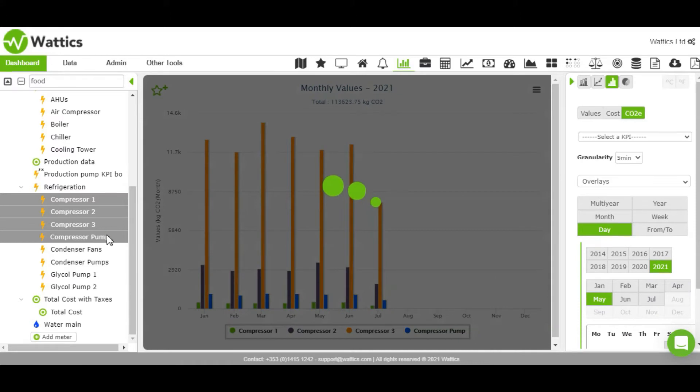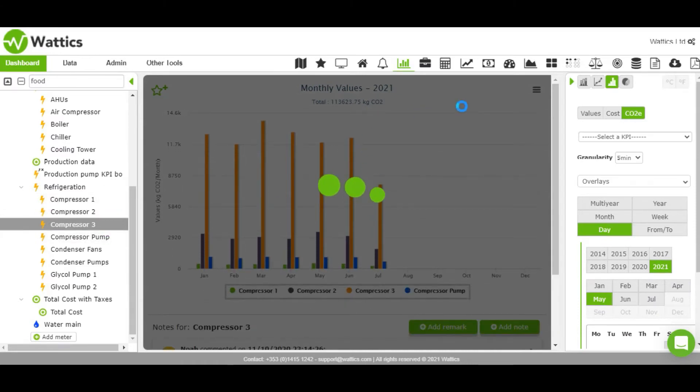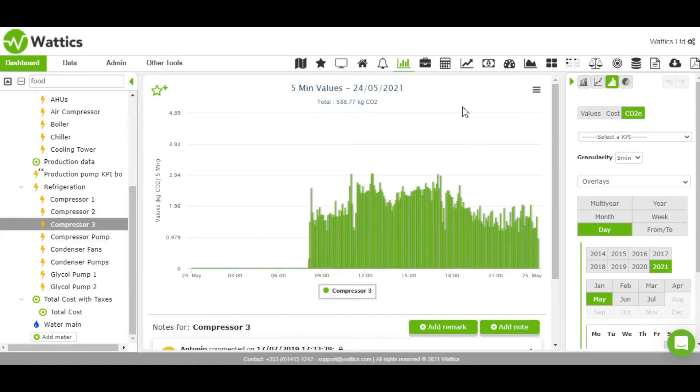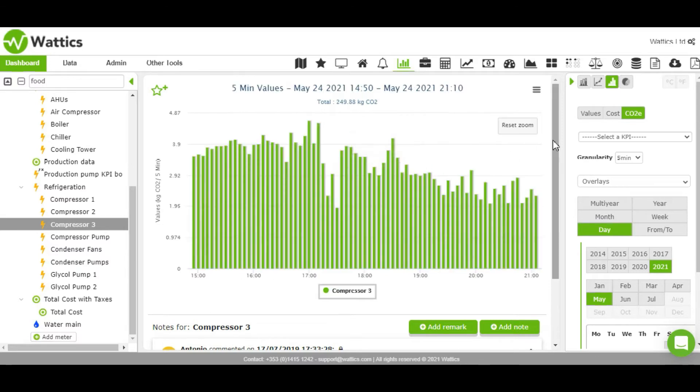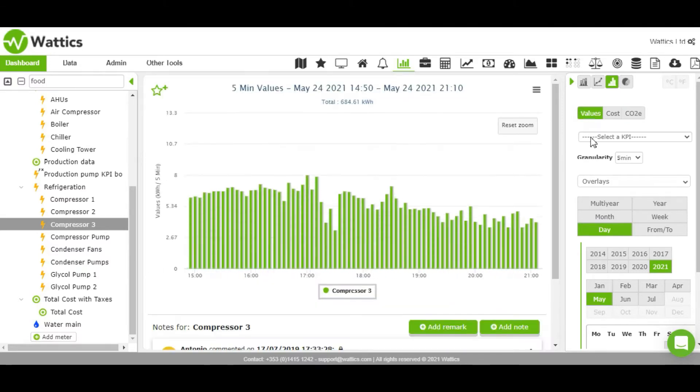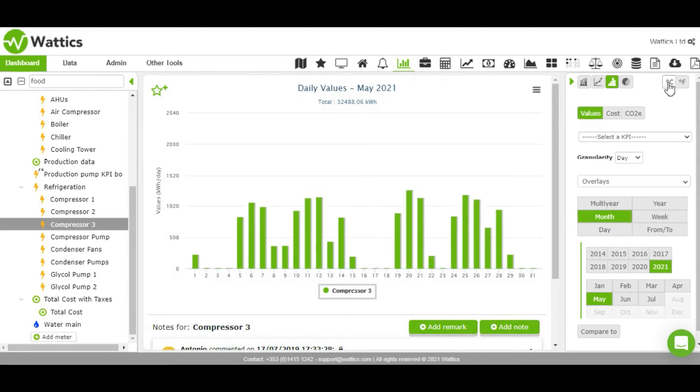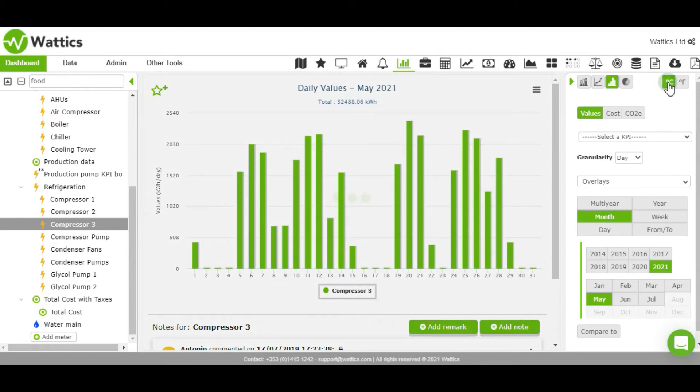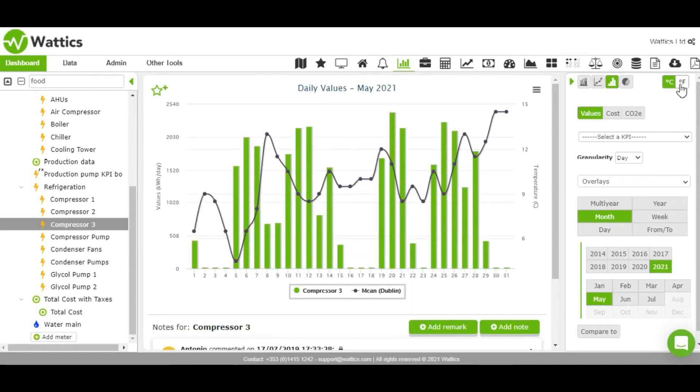Click and drag to zoom into a particular timeframe for more detail. If the month view is selected, a useful tool is to correlate with the outside temperature. The system automatically integrates the heating degree days data after inputting the physical address of the site.